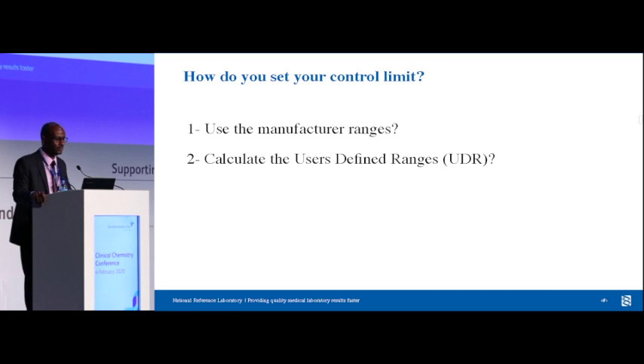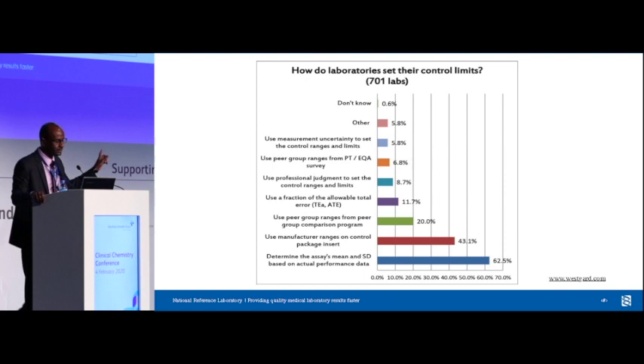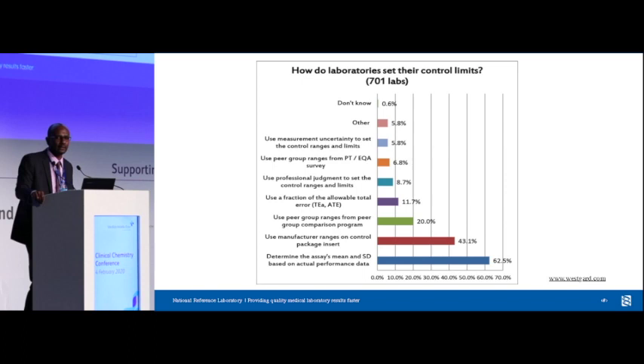The next survey question: how do you set your control limits? Do you use user-defined ranges where you calculate your QC, or the manufacturer's ranges? Interestingly, up to 43% of labs are still using manufacturer ranges. That is not good — they are way too wide. I can take a wild guess: those labs are most likely not accredited, because if they were, chances are they would be cited.